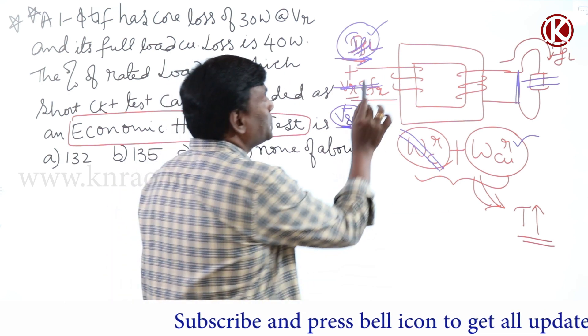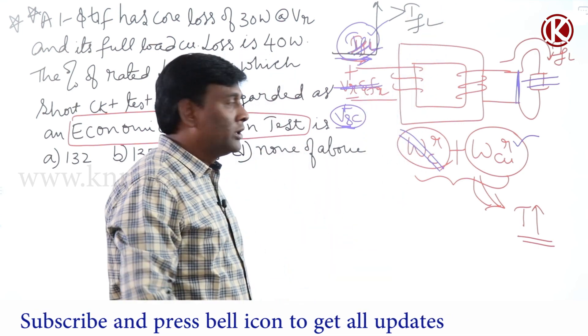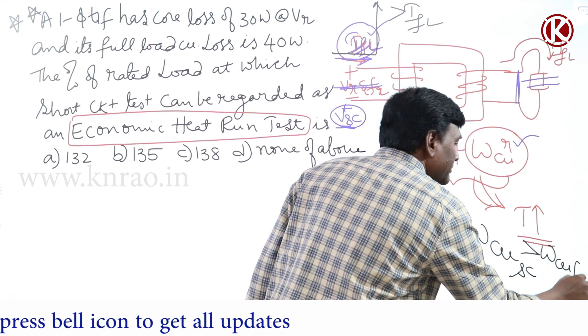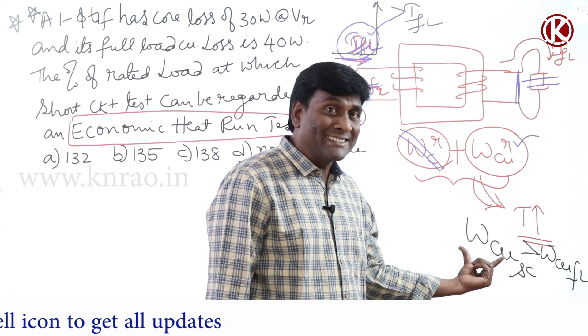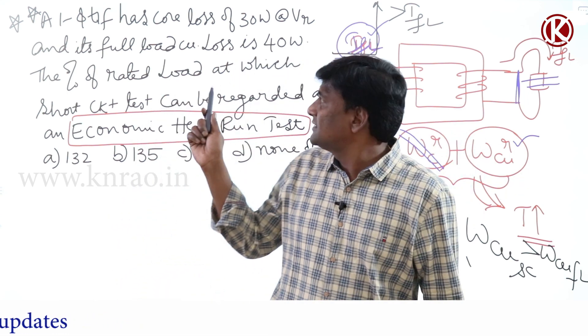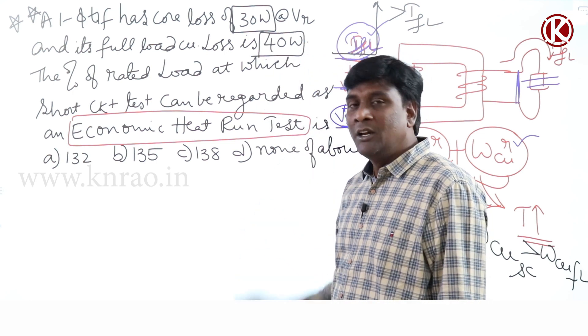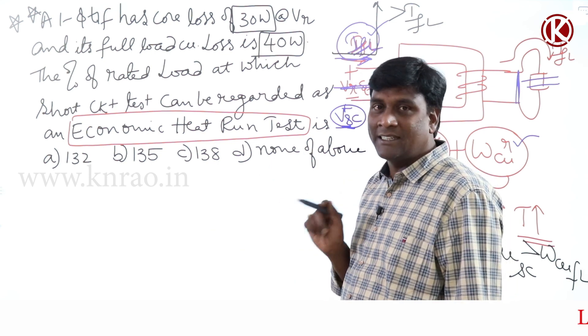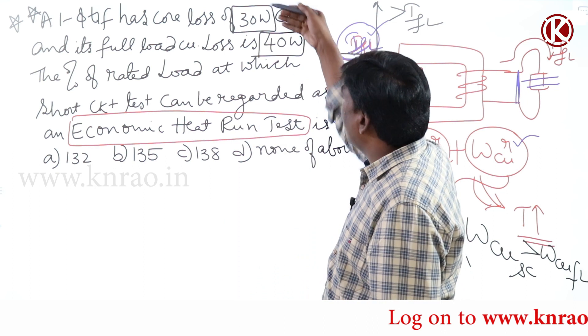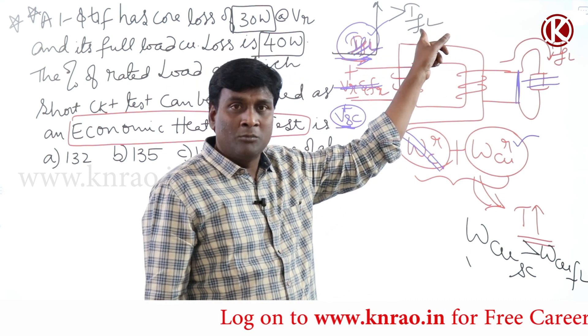Rather than conducting the test at full load, let me conduct this test at more than full load. Under that condition, my copper losses in SC test conditions will be more than copper losses at full load. For example, my copper losses in SC test at more than full load should equal core loss at rated conditions plus copper loss at rated conditions — meaning 30 watts plus 40 watts equals 70 watts. So I am injecting more than full load current.